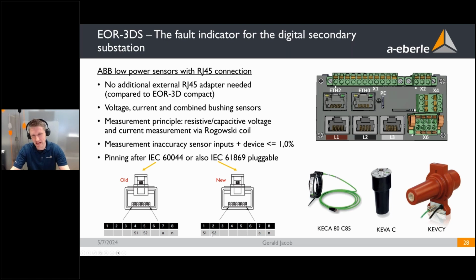But you don't have to care about this, because internally, when you order the device for ABB sensors, pins 1 and 4, as well as 2 and 5, are short-circuited in the device. So you can use sensors according to the old standard or to the new standard with our device.